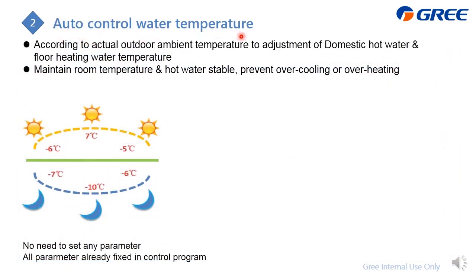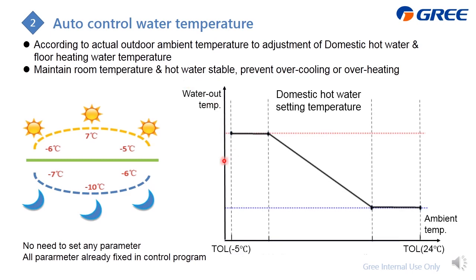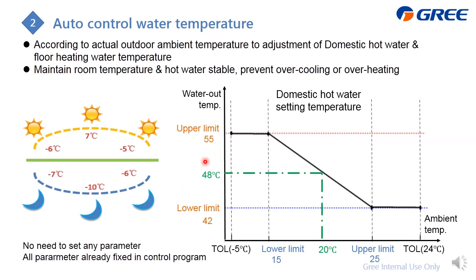Auto control water temperature. This function is according to your selection. If you activate this, the system will adjust the domestic hot water and floor heating water temperature automatically, based on the actual outdoor ambient temperature. So I will give you an example to explain this. For example, the system has already set the outdoor ambient lower and upper limit, and also the water out, which is for the domestic hot water, the upper and lower limit. For example, if today it detects the outdoor ambient is 20 degrees, then it can automatically calculate that today's domestic hot water setting temperature is 48 degrees. For this function, there is no need to set any parameter. All is controlled by the system, and all the parameters are already fixed in the control program.